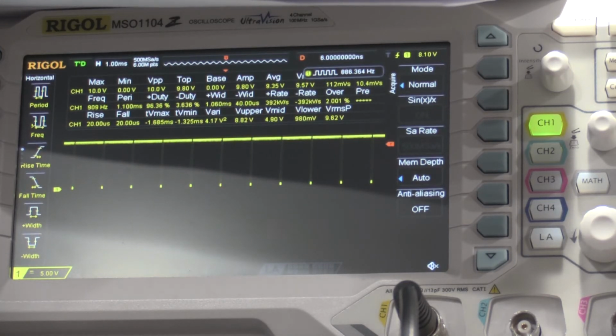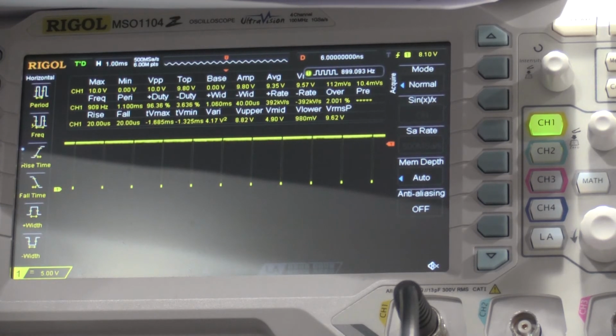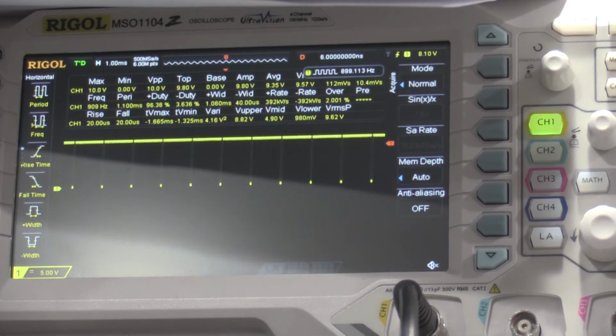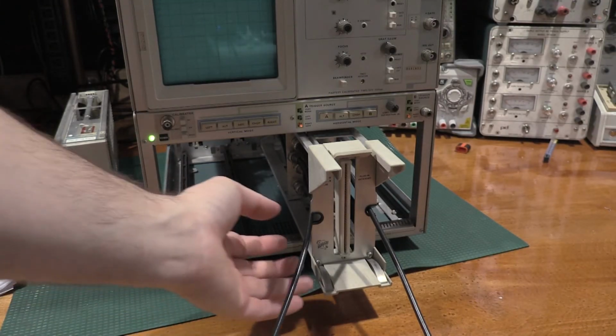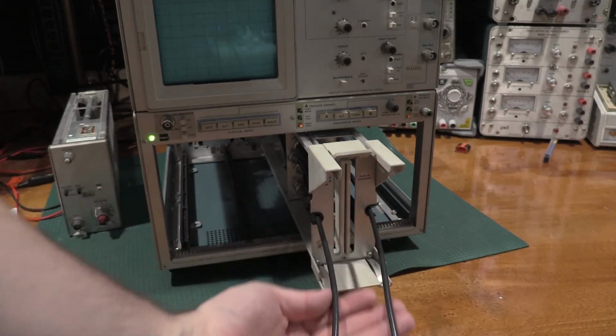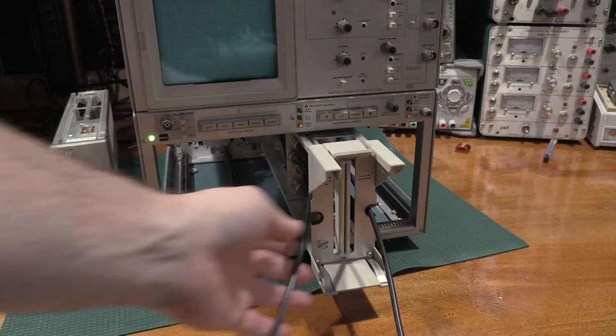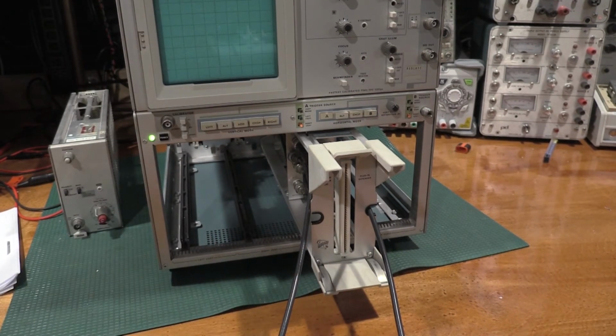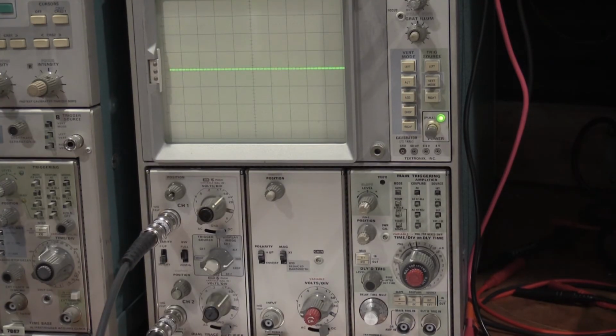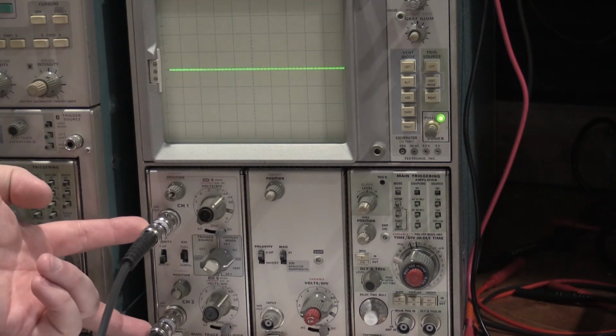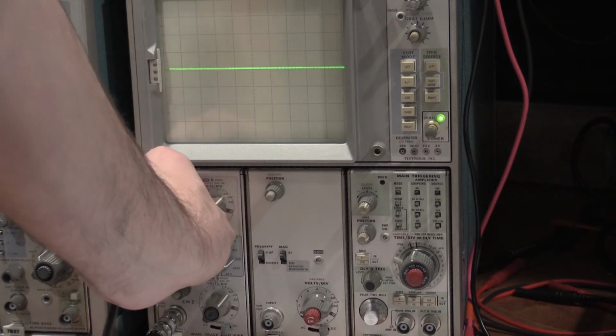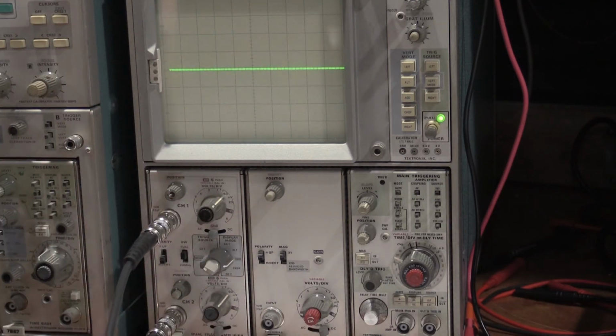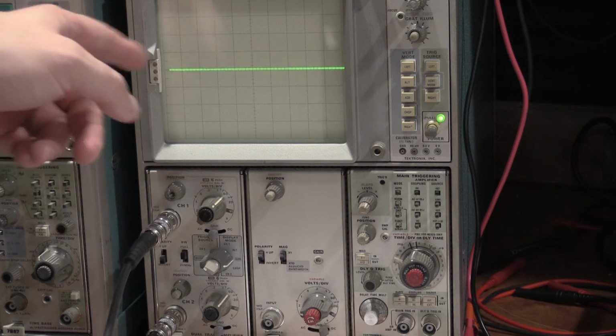As well as gate on A. And for the last step, it wants us to check the Graticule Illumination, but since we did the LED modification, we know the Graticule Illumination works just fine. Okay, for the trigger mode, I have the trigger selectors coming out of A20 and B20. Those come over here to the 7603, and they are both terminated into 50 ohms. Here's our ground reference setting, right in the center of the screen.